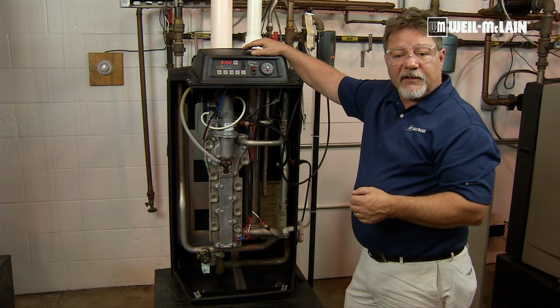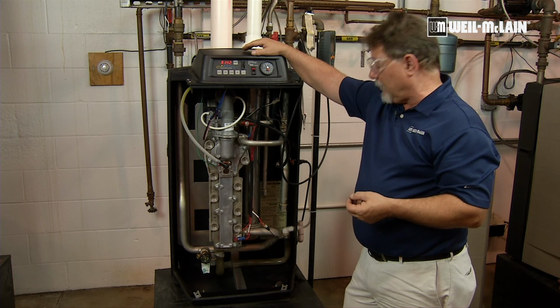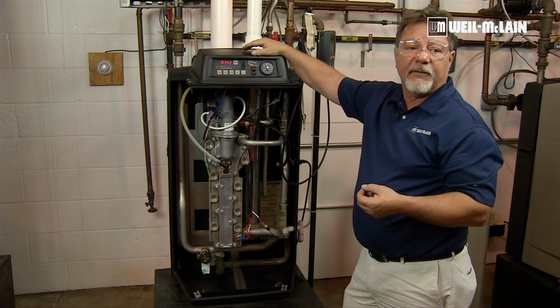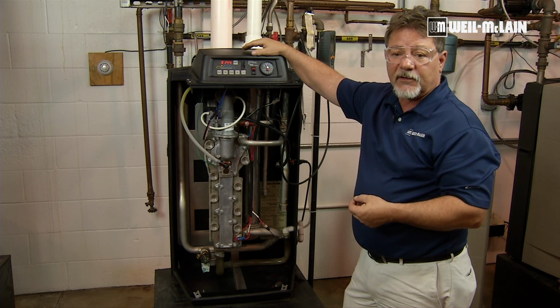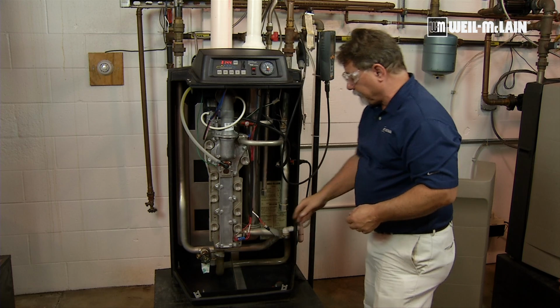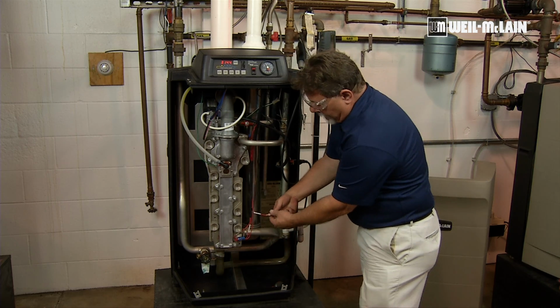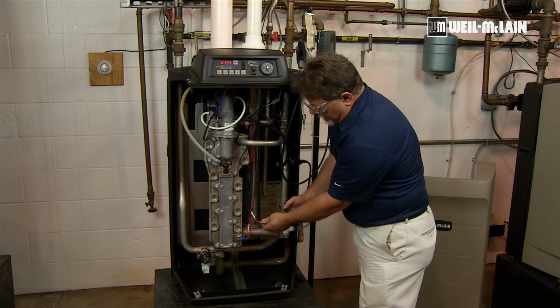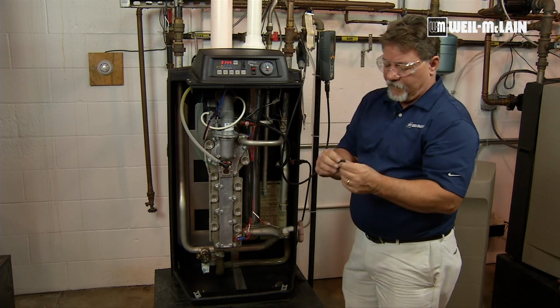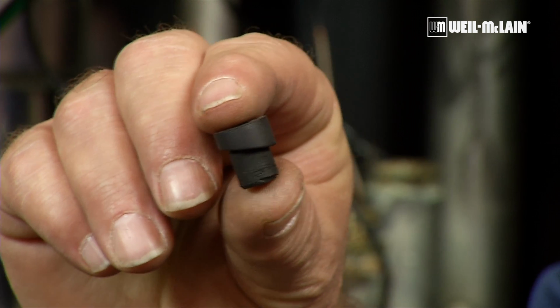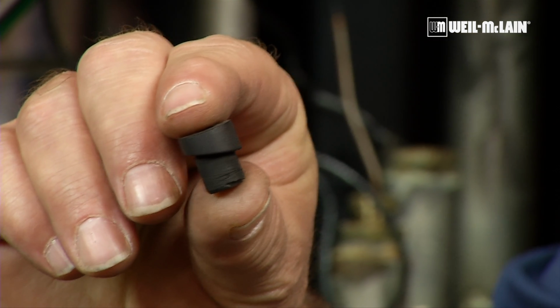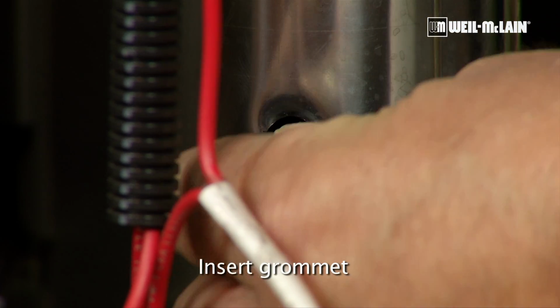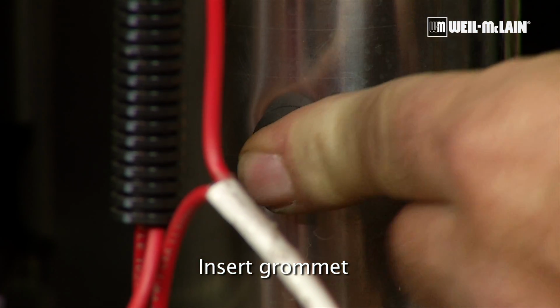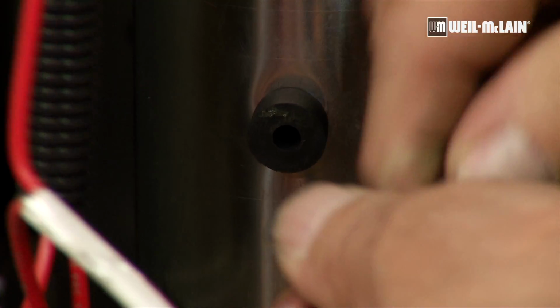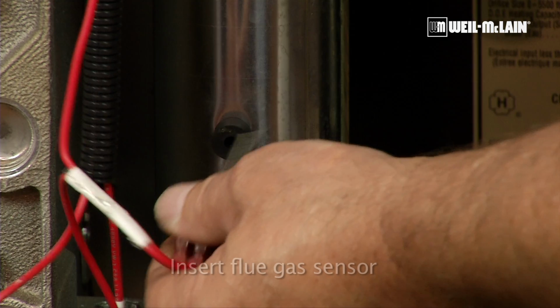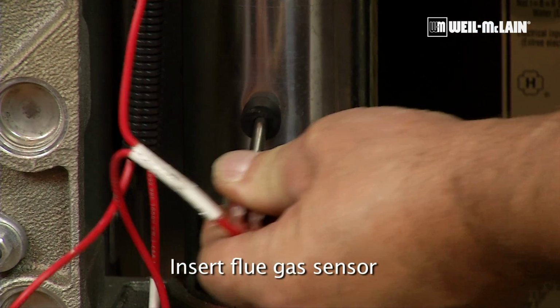We've completed our combustions. We just need to restore the boiler now, and so we're going to reinstall the flue gas temperature sensor, and we'll install the jacket door. Now the flue gas temperature sensor has a grommet that seals the sensor gas tight. Again, there's a little slant built into it, and we simply want to make sure that the probe, when it's inserted, points upward. So we're going to put a little bit of moisture on the sensor and insert it.